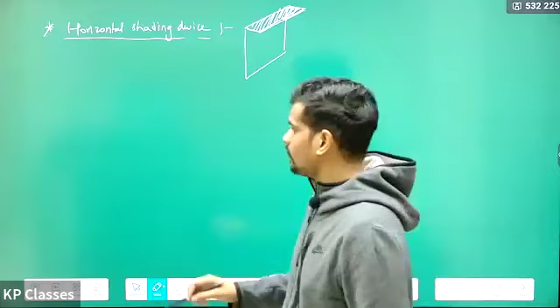Horizontal shading device is basically something which, let us say this is a window. A horizontal shading device is something which you project at the lintel level. So it is a horizontal element like a chhajja. At the lintel level, you provide a projection. That's called a horizontal shading device. How do you find out the projection length of a horizontal shading device? The projection length of horizontal shading device is calculated in terms of tan of the vertical shadow angle.